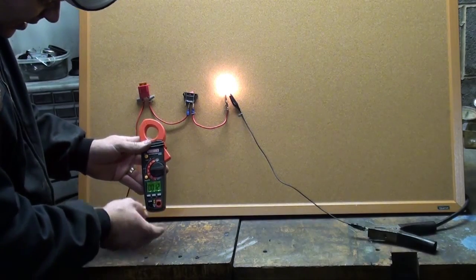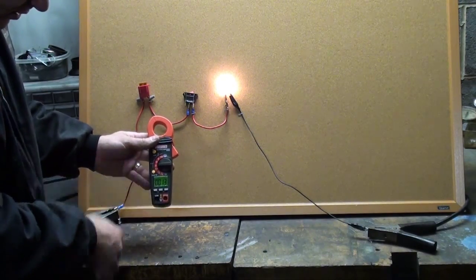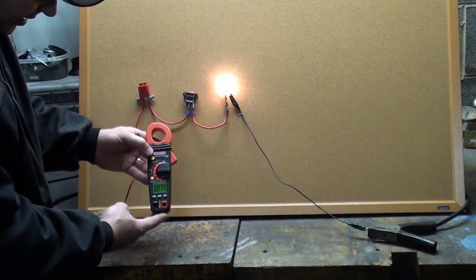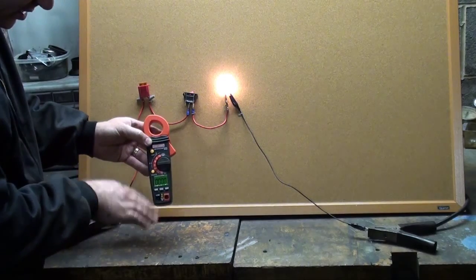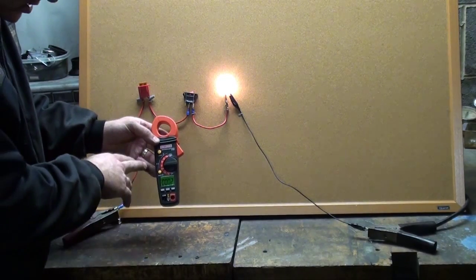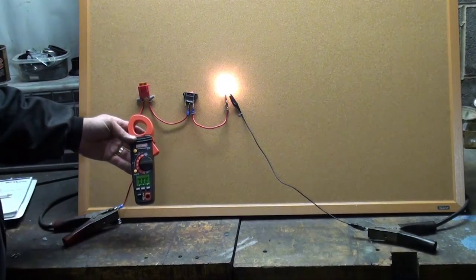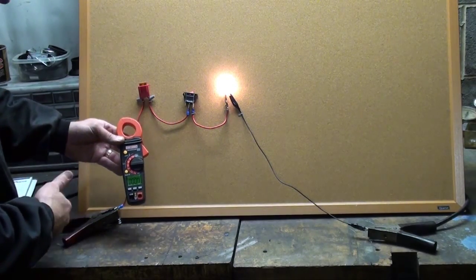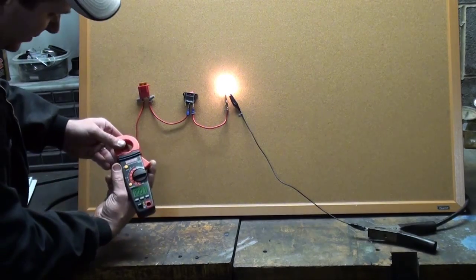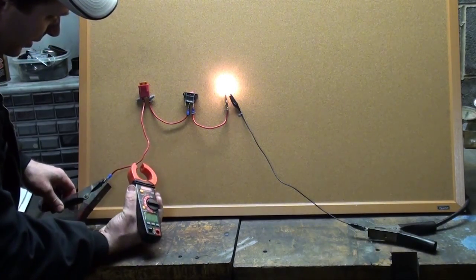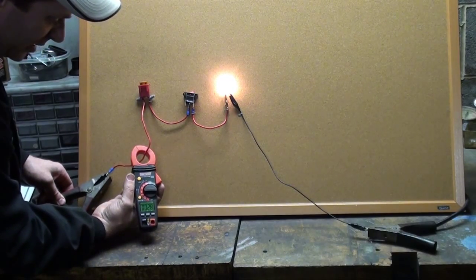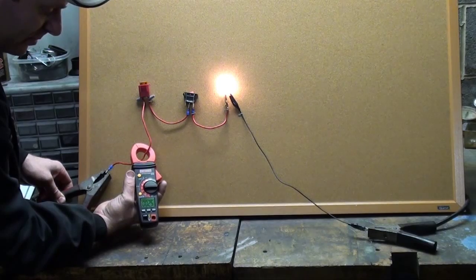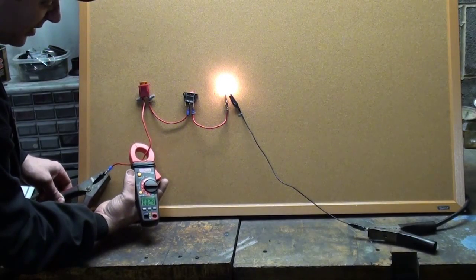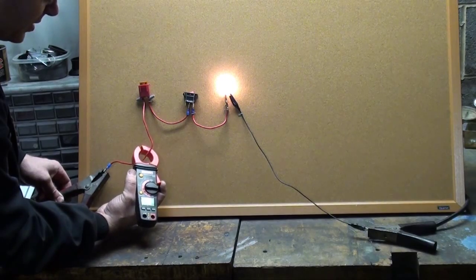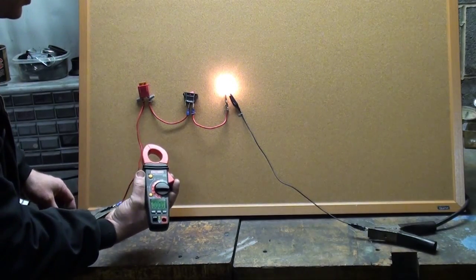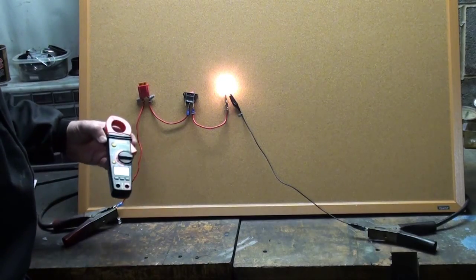On this one, as you can see, there's a lot of stray reading - the numbers fluctuating between 12 and 13. When you're doing DC, they recommend you try to zero it, which just hides that ghost fluctuation close to zero for you. Let me demonstrate how this works. You simply clamp it around the conductor, trying not to get in your way. And as you can see, pretty much the same range as the other DVOM, but I don't have to open the circuit.